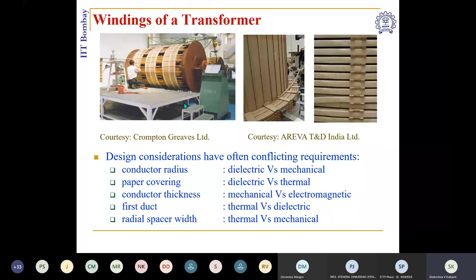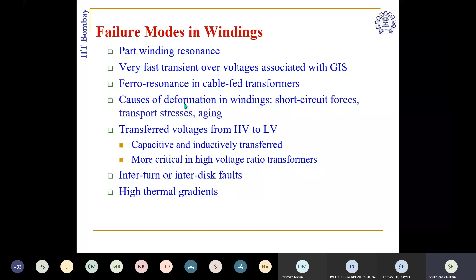design windings. So what are failure modes in windings? Part winding resonance, which we already discussed, very fast transient voltages, resonances, short circuit forces, transfer voltages from HV to LV windings, particularly in high voltage ratio transformers. If suppose you have a large generator transformer, 21 kV by 400 kV, then transfer voltage from 400 kV to 21 kV can be substantial, and they need to be taken care of. Interturn or interdisc faults and high thermal gradients.